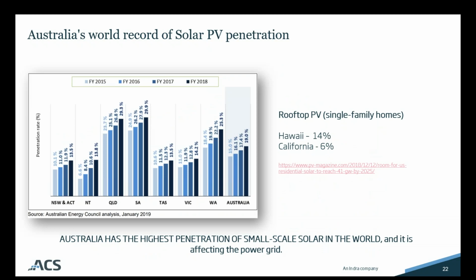So why Australia? Well, Australia has the world's highest penetration of small-scale solar, as you can see from the graph in the slide, where each state is indicated here in the graphs, and you see the growth of the penetration during the years. So in terms of installed power, it's almost 1/7 of the total capacity of the energy market in Australia's East Coast. So, and it is undispatchable. In the USA, to give an example, the highest penetration is in Hawaii, and it's just 14%. So a value that Australia had only 4 years ago, if you can see from the graphs. So in only 4 years, Australia has changed the way power flows across the grid.